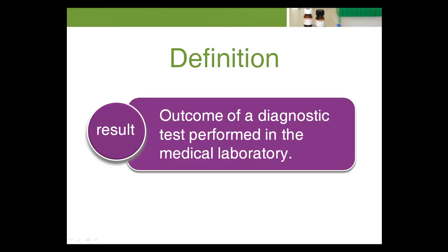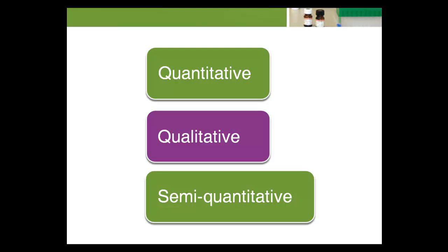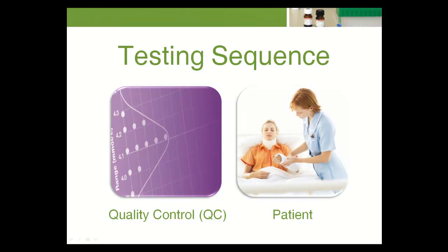When a diagnostic test is performed in the medical laboratory, the outcome of the test is a result. The result may be a patient result, or it may be a quality control (QC) result. The result may be quantitative (a number), qualitative (positive or negative), or semi-quantitative (limited to a few different values). QC results are used to validate whether the instrument is operating within predefined specifications, inferring that patient test results are reliable.